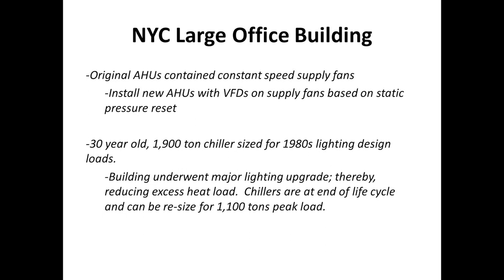The unit was already oversized. So this normally wouldn't have been cost effective, except that the chiller was already 30 years old and needed replacement. But by evaluating and modeling the current conditions, we could recommend that they resize the chillers for 1,100 tons at peak load as opposed to 1,900.